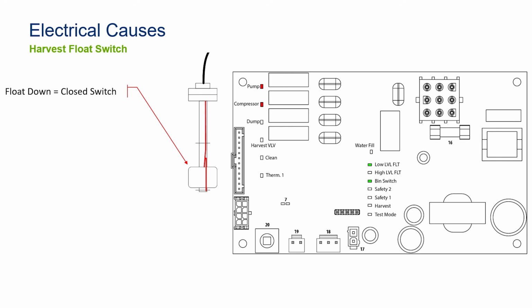If it stays that way the entire freeze cycle, even if we're out of water, you're not going to go into harvest. The harvest float's job is to tell you, I've gone closed, which means I must have consumed all my water into ice, it's time to harvest. Boards can do one of two things, everybody. It can either do what it's programmed to do, that's one thing, or what an input device tells it to do in conjunction with its programming.